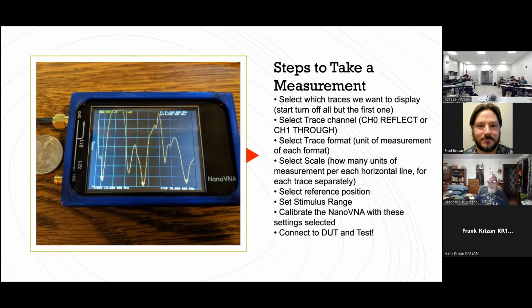You'll want to select your scale, and then you'll want to select your stimulus range. The stimulus range being your, say, 14 or 13.9 to 14.4, or your 2 to 30, whatever that may be. Because when you do the calibration, it is going to take that information and it's going to be looking for that stimulus range. Let me phrase that. It's going to be calibrating to that stimulus range.